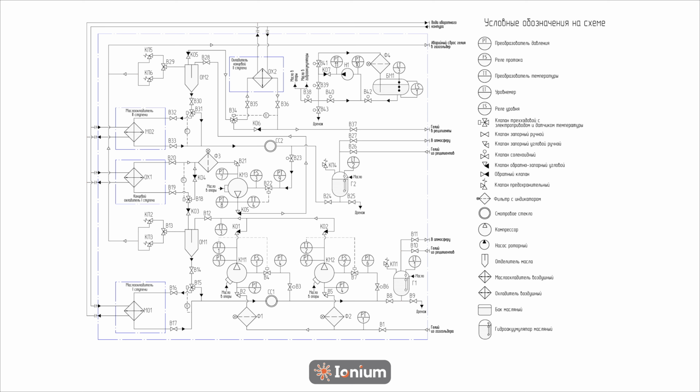It's beneficial to include extra cooling, maintaining a steady temperature of about 16 degrees Celsius, using the water from the chiller's intermediate circuit. The evaporators in the vapor compression refrigeration system are cooled. The nominal thermal load on the chiller's intermediate circuits is around 65 kilowatts for a helium flow rate of 1 kilogram per second. The refrigerant used in the circuits of vapor compression machines that use screw compressors with frequency control is either R407C or R134A. Chillers located in the machine room circulate softened technical water through the intermediate circuits instead of a glycol solution.